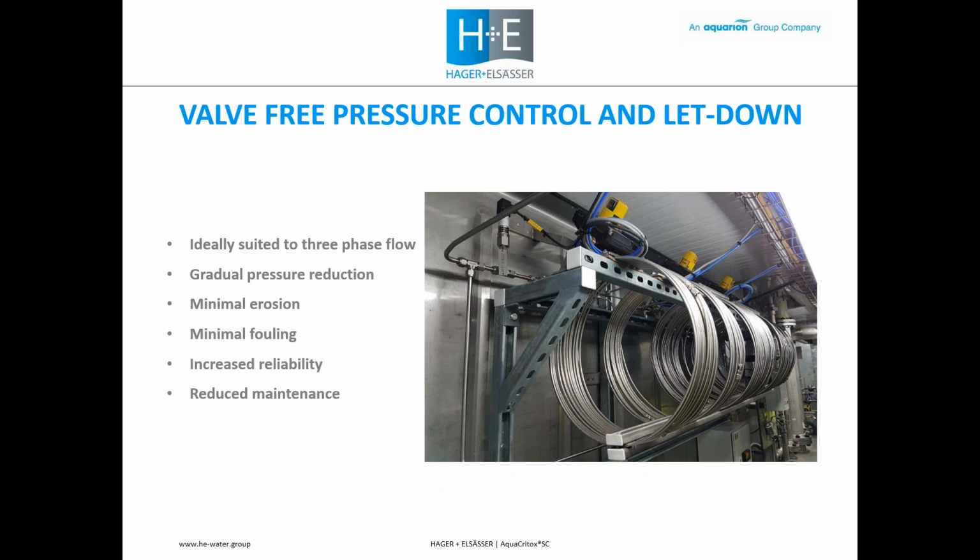So rather than dropping the pressure across a single point control valve, the pressure is let down gradually across coils of capillary. So the fluid flow is continuous. This ensures that we don't have issues with corrosion and solids deposition and blockage, and also means that the aggressive nature of this fluid doesn't cause excessive erosion on these tubes, leading to very long service life and minimal maintenance requirements.